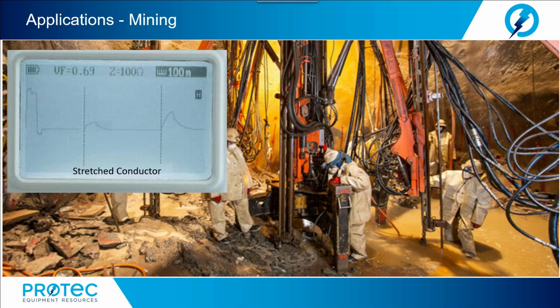Due to the distances involved, these cables, especially those used for telecommunications, become stretched and are likely to fail. Simple numeric or graphical TDRs are used to test cable integrity and to locate failures such as opens or short circuits.